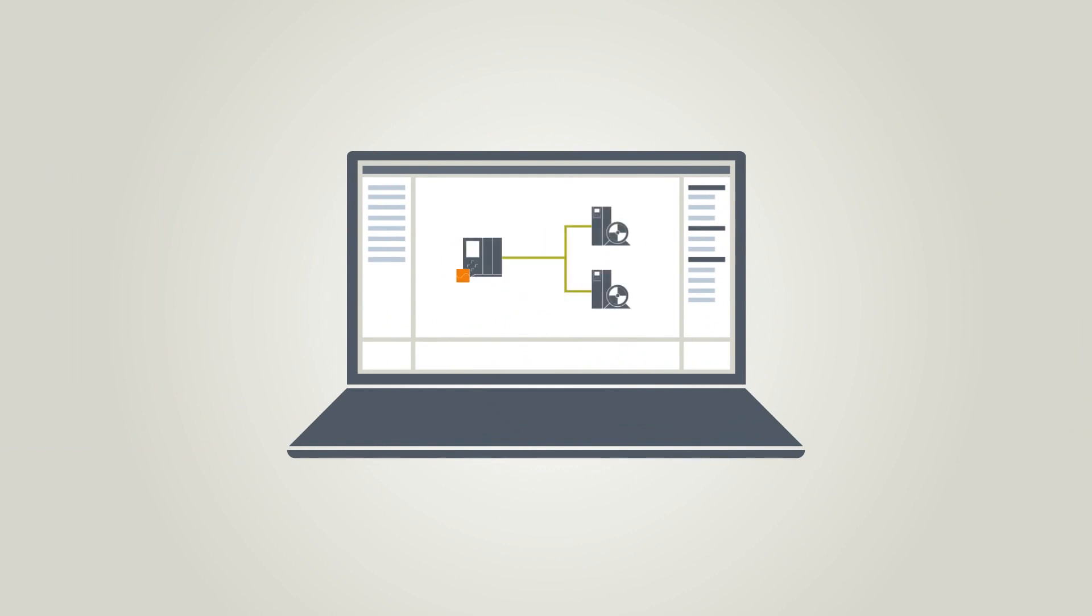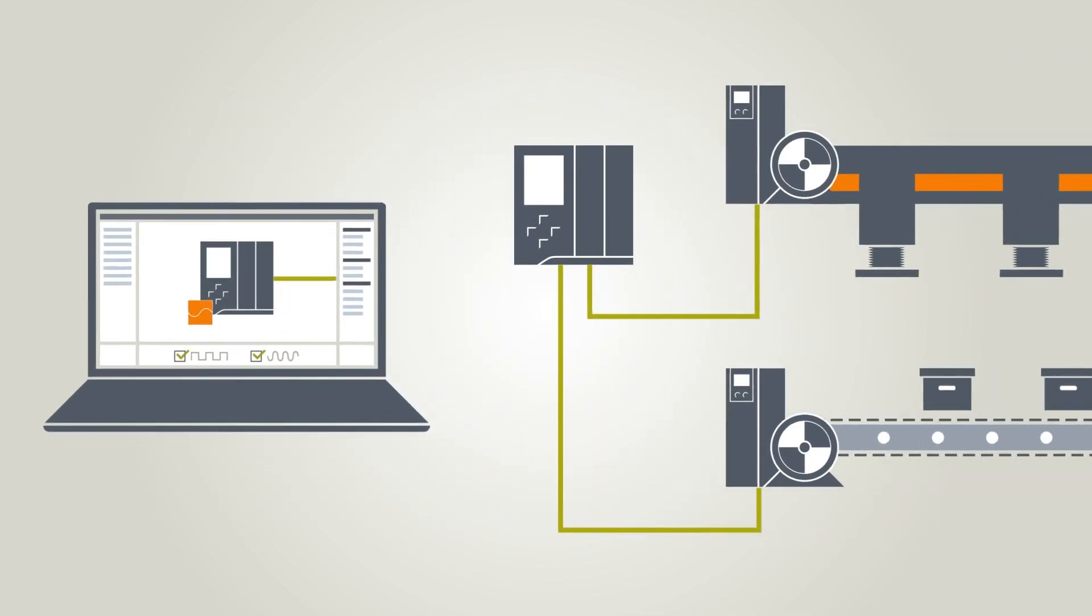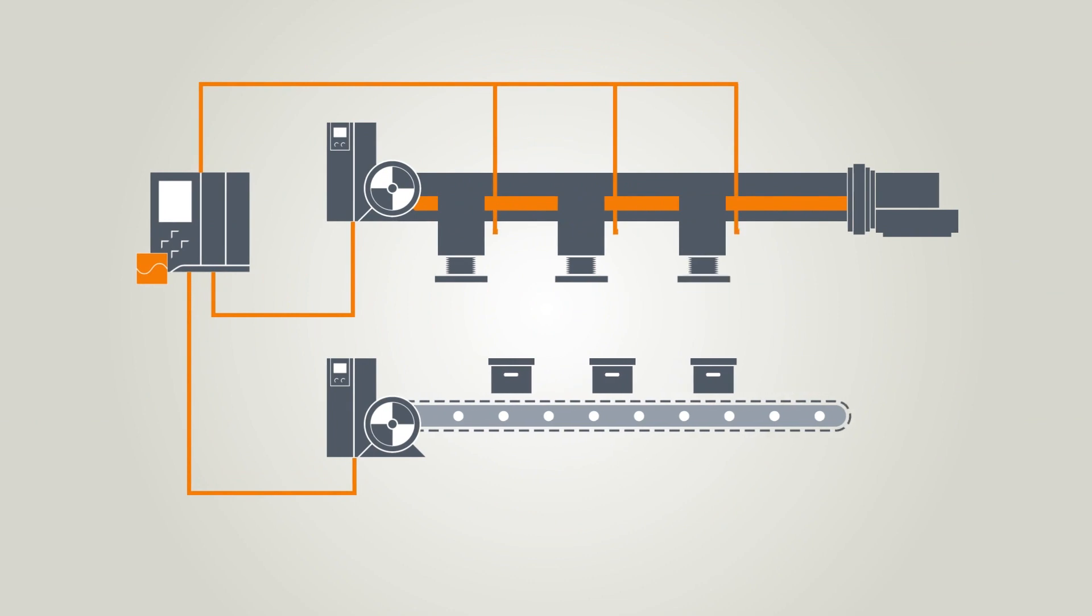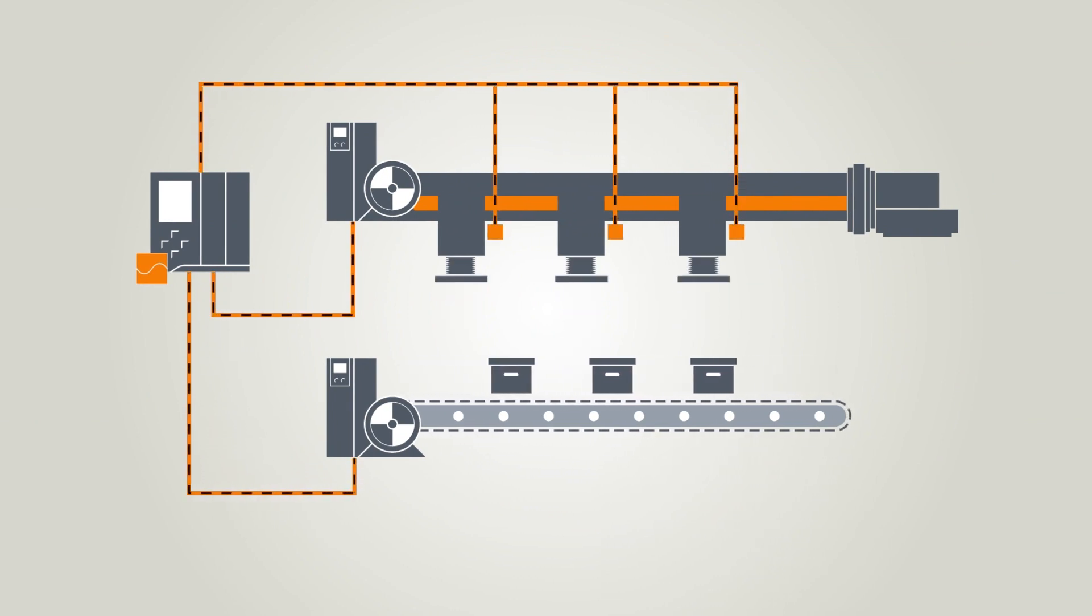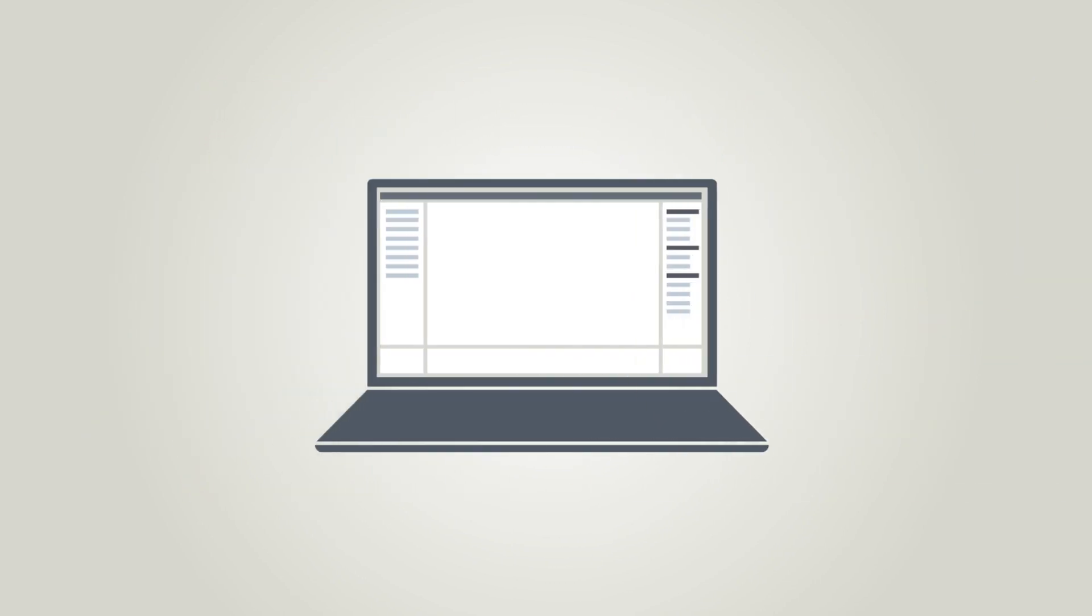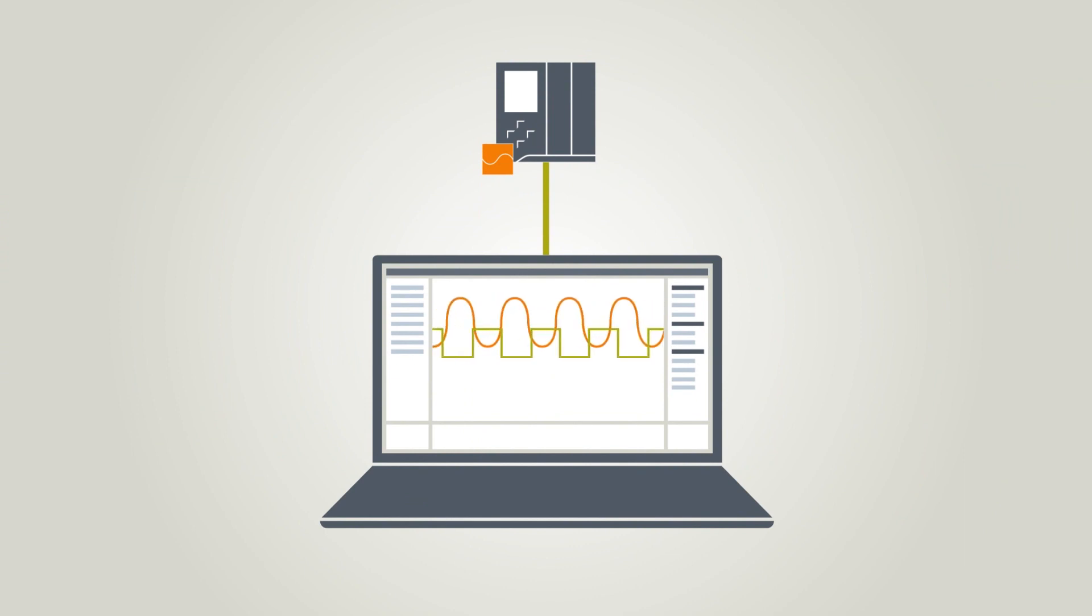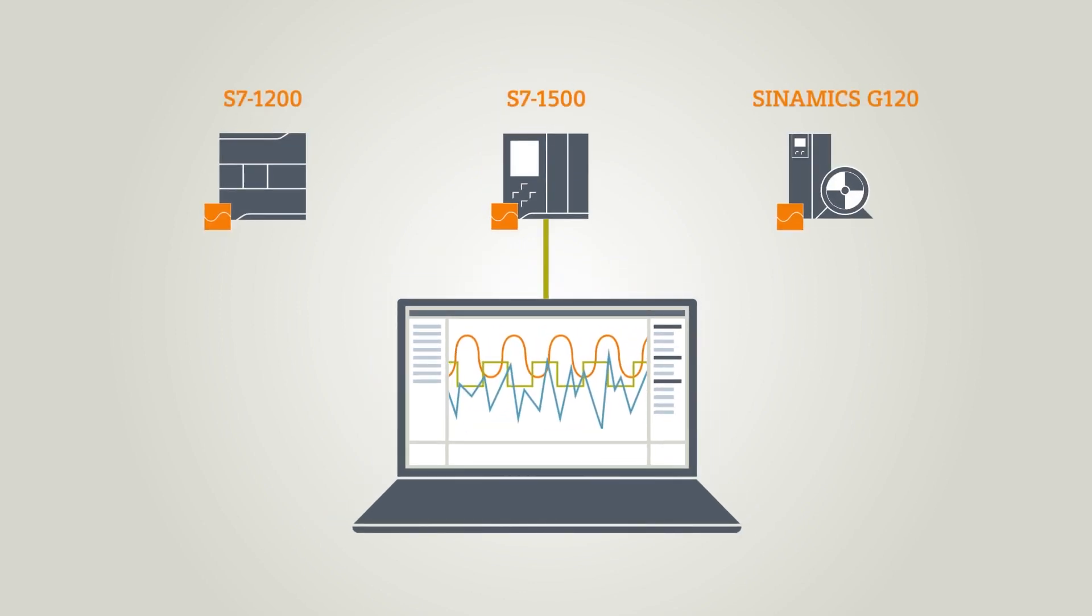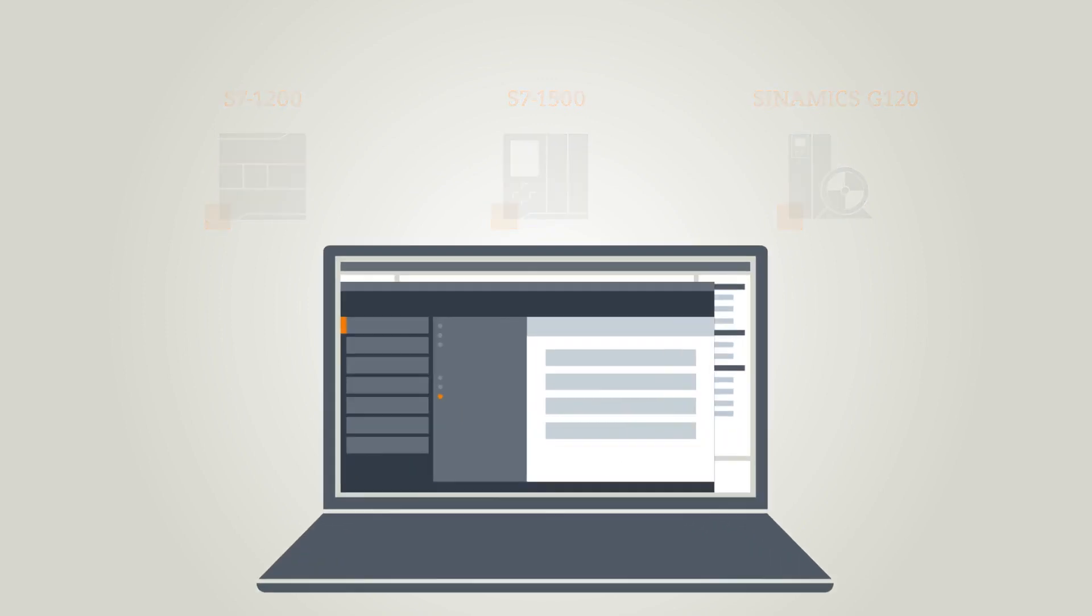Simply specify the binary and analog variables of the device that you want to record in the trace configuration. The trace is then transferred to the controller and activated. As soon as the trigger condition is fulfilled, the values are recorded in the controller independently from the TIA Portal. The TIA Portal offers a whole range of options for evaluating the measurement using curve diagrams or signal tables. The trace is integrated in the device firmware, so no extra hardware is required.